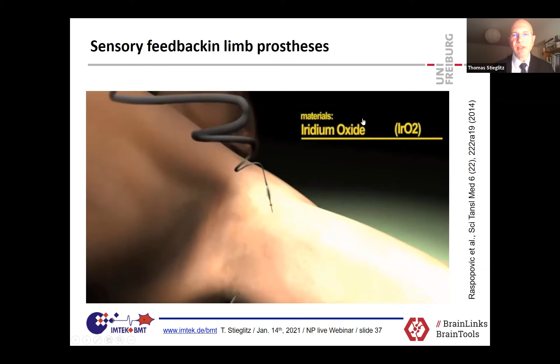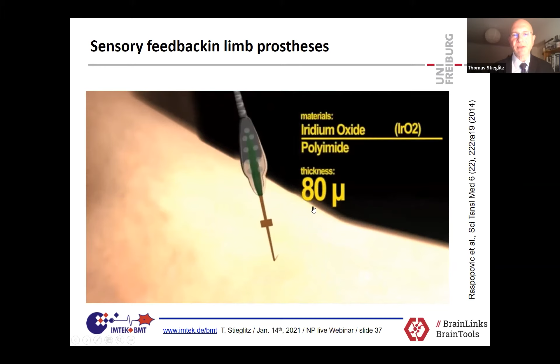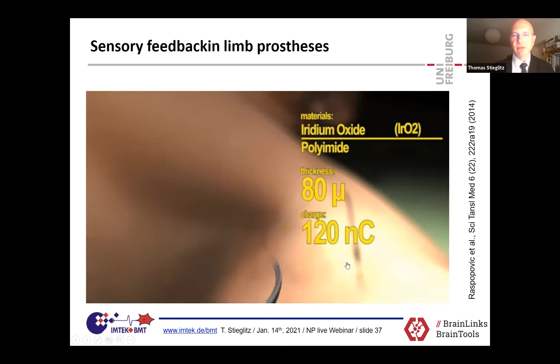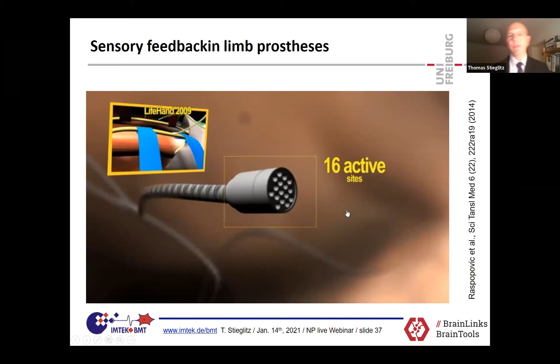The electrodes have an iridium oxide coating in polyimide embedded. This is not the thickness, but the diameter of the electrodes, 80 microns. They can deliver 120 nanocoulombs of charge. And we have 16 active sites, 7 of them looking to the left-hand side, 7 to the right-hand side, and 2 counter electrodes to close the electrical circuit.